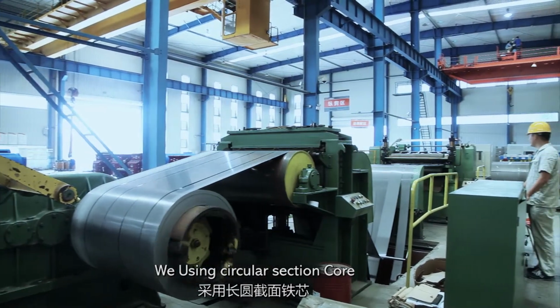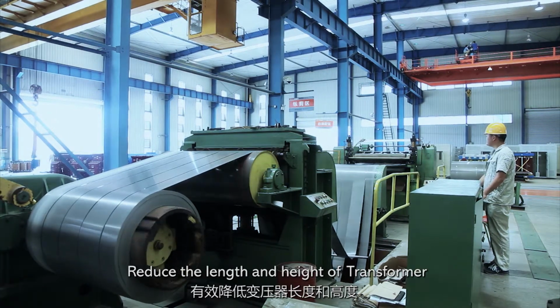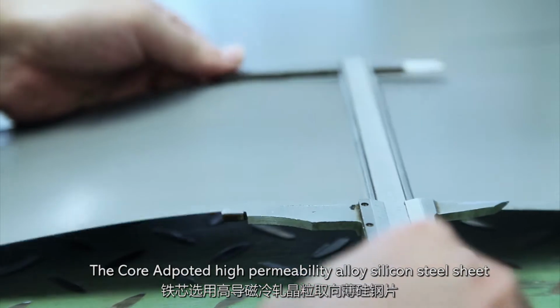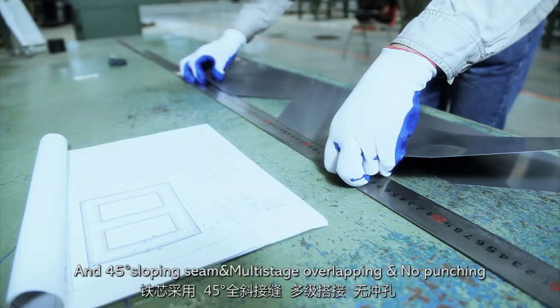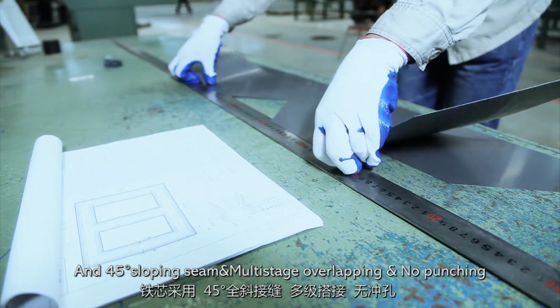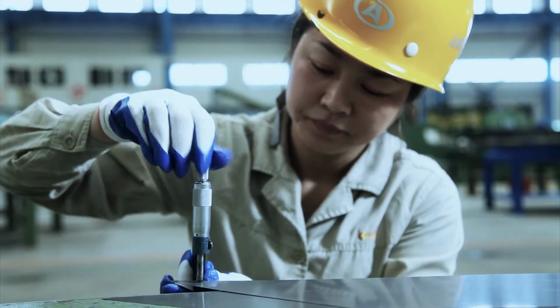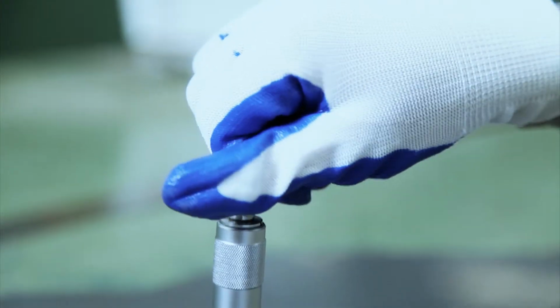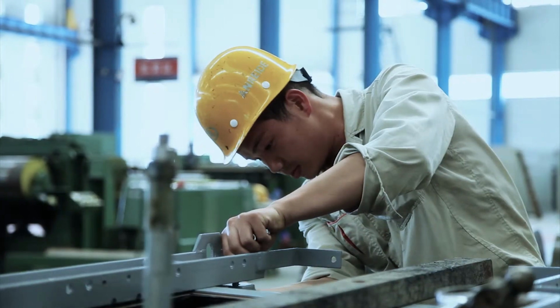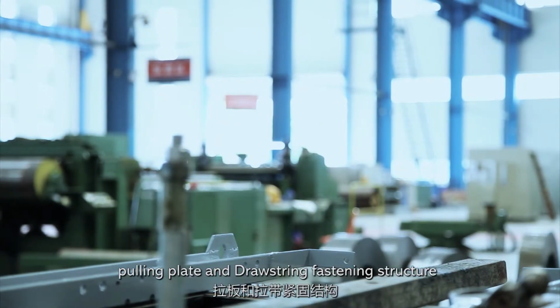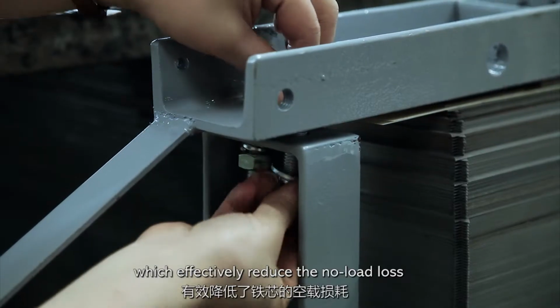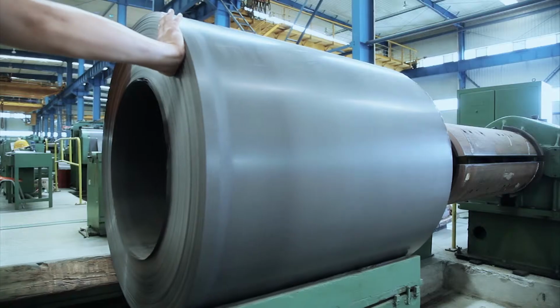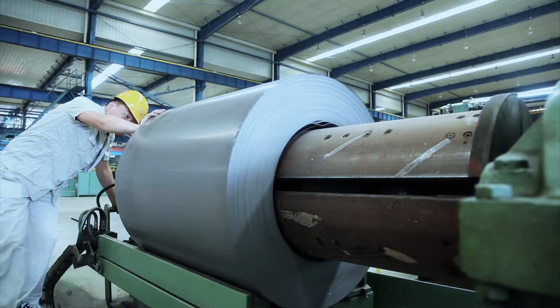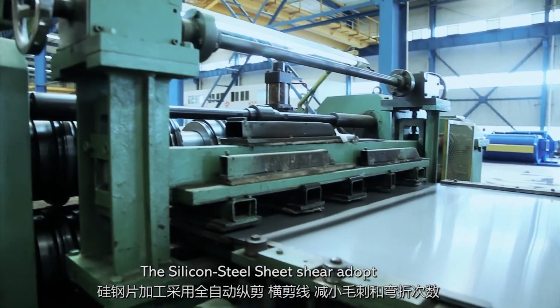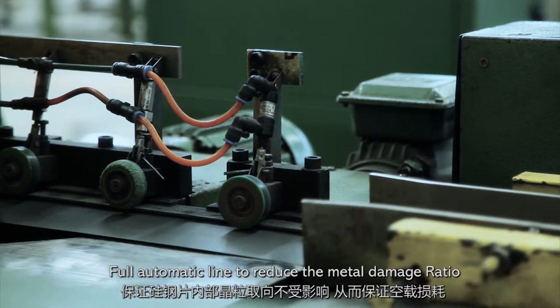We are using a circular section core to reduce the length and height of the transformer. The core adopts high permeability alloy silicon steel sheet, 45-degree sloping seam, multi-stage overlapping, and no punching. Pulling plate and drawstring fastening structure effectively reduce the no-load loss. The silicon steel sheet shear adopts a fully automatic line to reduce the metal damage ratio.